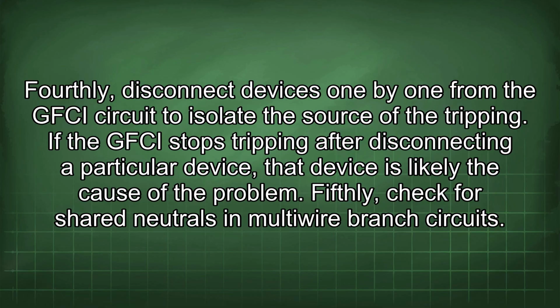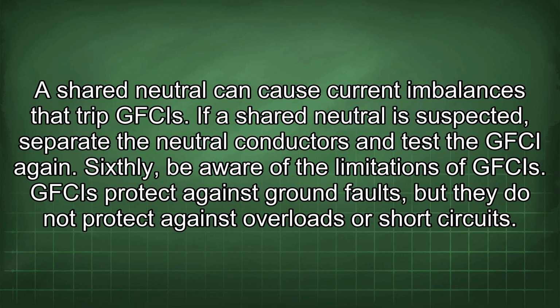Fifthly, check for shared neutrals in multiwire branch circuits. A shared neutral can cause current imbalances that trip GFCIs. If a shared neutral is suspected, separate the neutral conductors and test the GFCI again.